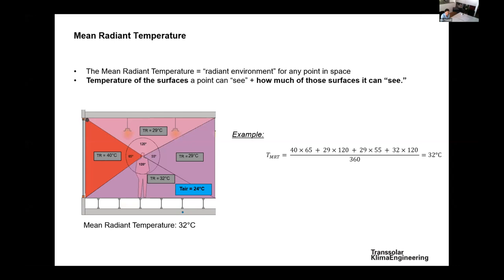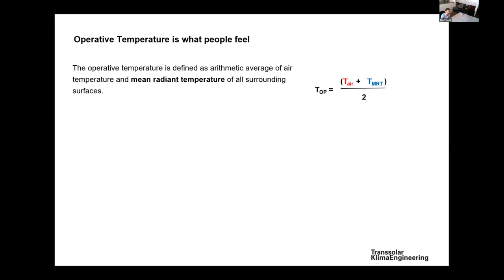The concept of mean radiant temperature is linked to operative temperature. What people feel is approximately half radiation and half convection, with convection corresponding to air temperature. That's why a new definition of temperature was developed — operative temperature — representing what people actually feel. It's defined as: operative temperature equals air temperature plus mean radiant temperature, divided by two.